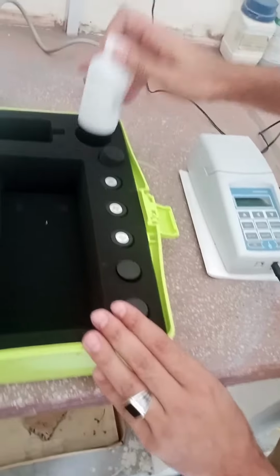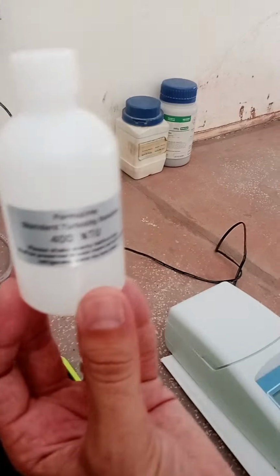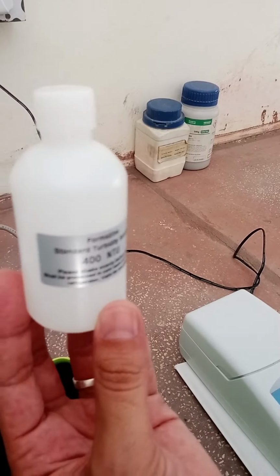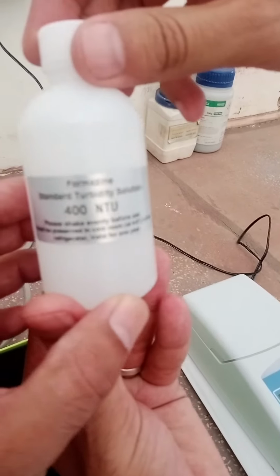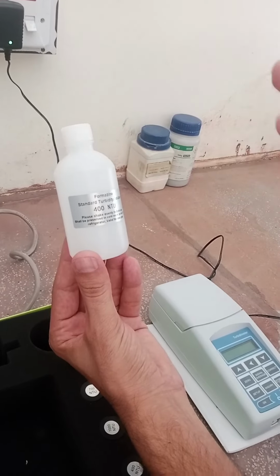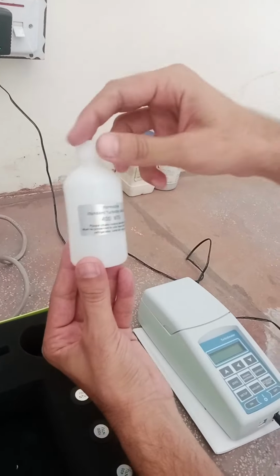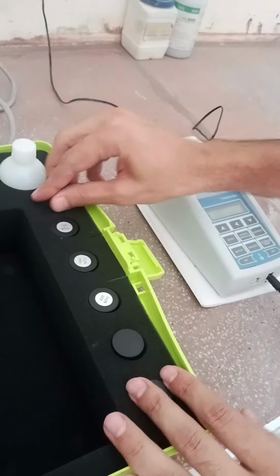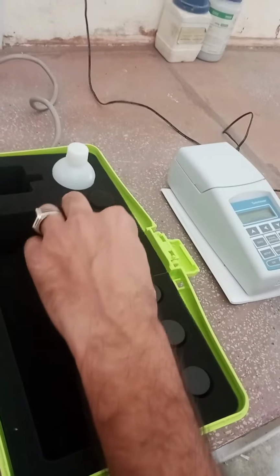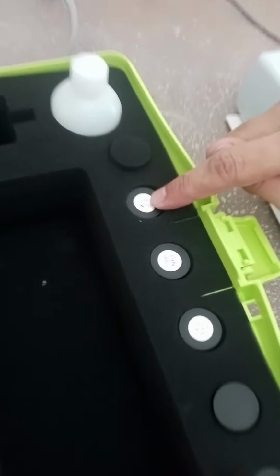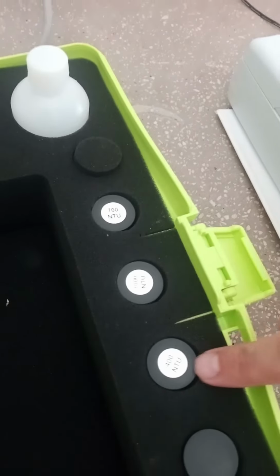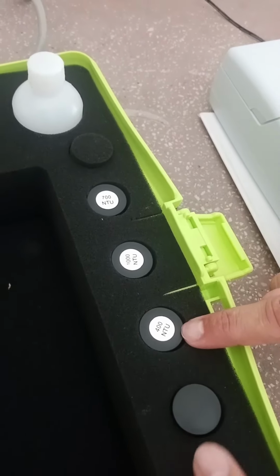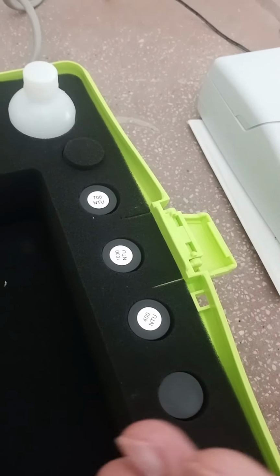It's a Formazine sample, and that is used to make the samples by adjusting the amount of this Formazine in the water, pure water, you can say, or distilled water. These are the samples: 700 NTU, 1000 NTU and 400 NTU. These are samples that have a specific NTU number.